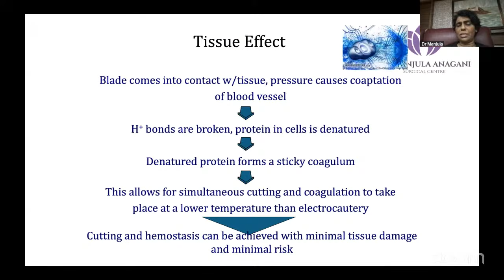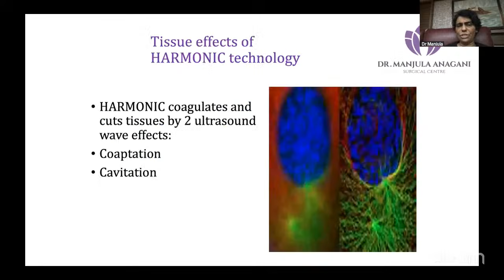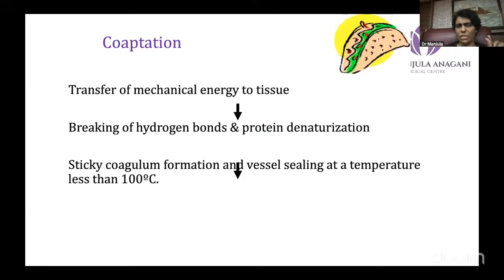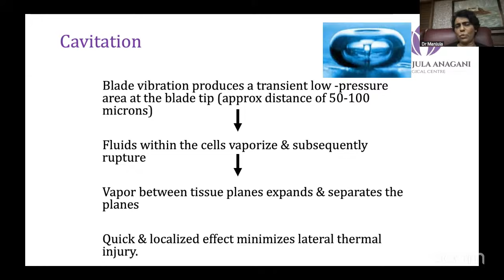So there are two effects, that is coaptation and cavitation, which are happening. It is the transfer of mechanical energy, when there's coaptation, that breaks the hydrogen bonds. Coagulation happens at 100 degrees again here. Then the cavitation effect happens at the tip of the blade. The fluid will start vaporizing. The vapor will start forming the tissue planes, and a quick and localized effect will be there.